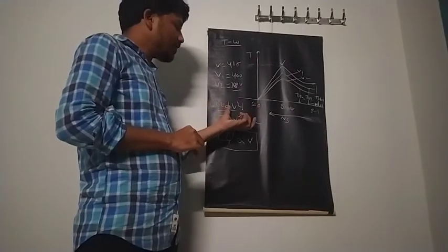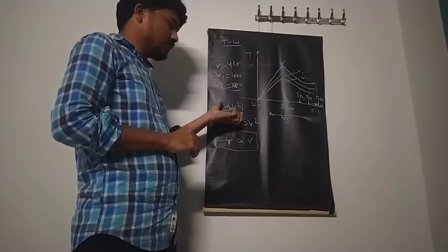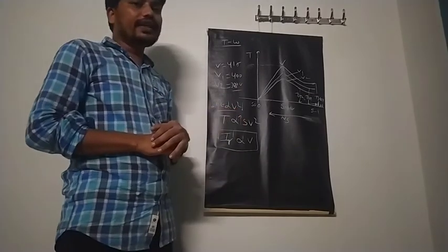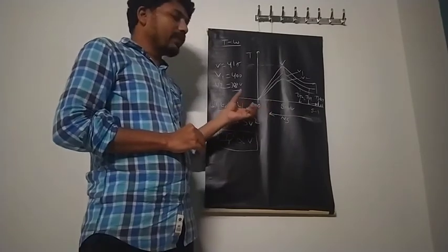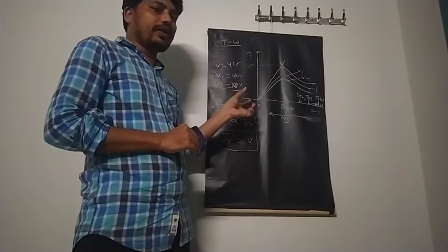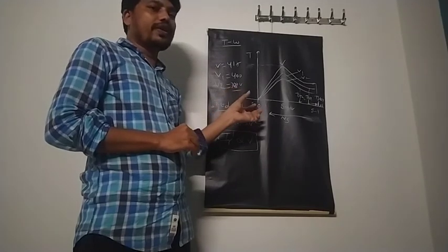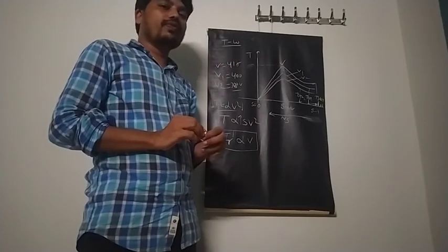So overall, whenever you are decreasing the voltage to maintain the torque constant, slip increases. As the slip increases, therefore speed must decrease. So in case of pump or fan type of drives, the torque reduces and also speed reduces. Therefore it is best suited for fan and pump type of drives.